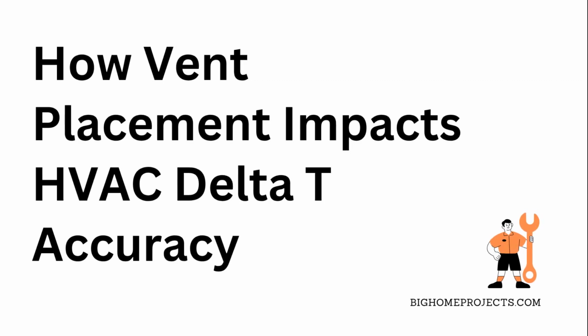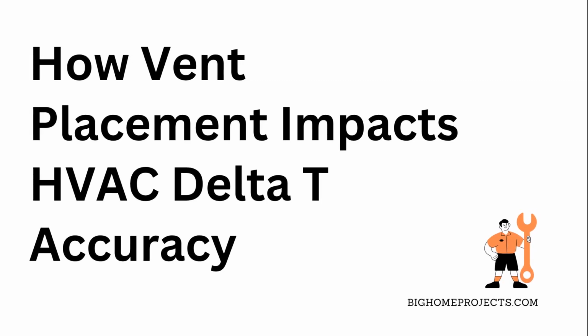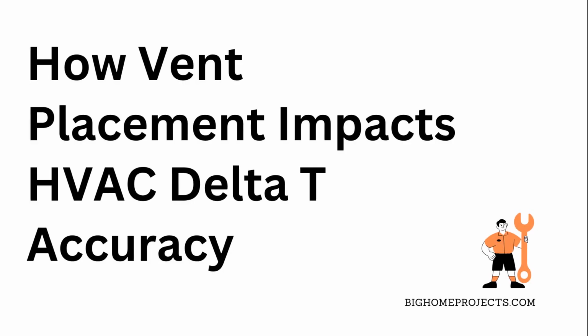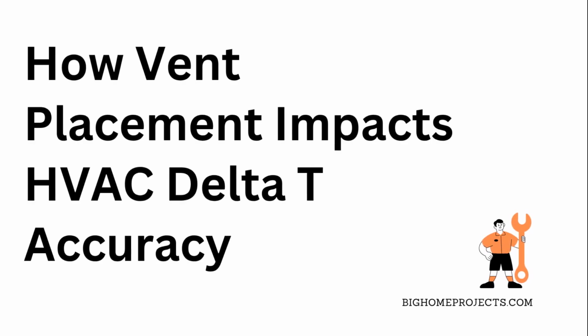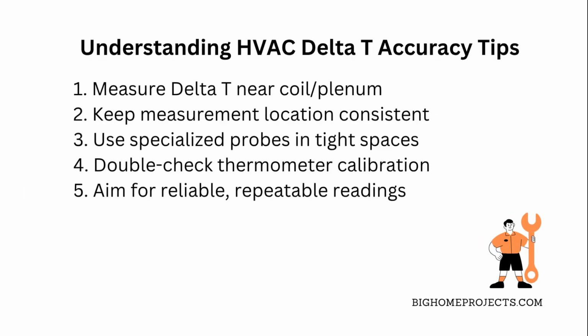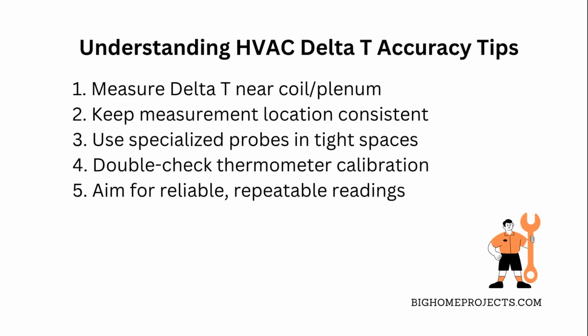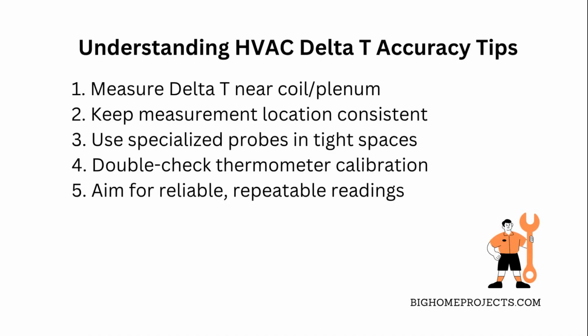HVAC Delta T readings can totally throw you off if your return or supply vent placement is off, especially in tight spaces where every inch counts. So, here's the thing, Delta T is just the temperature difference between your supply air and return air, right?